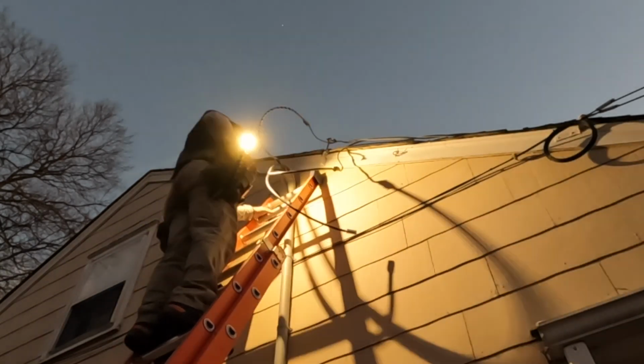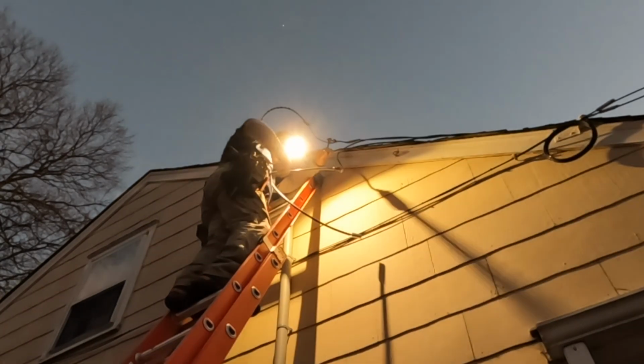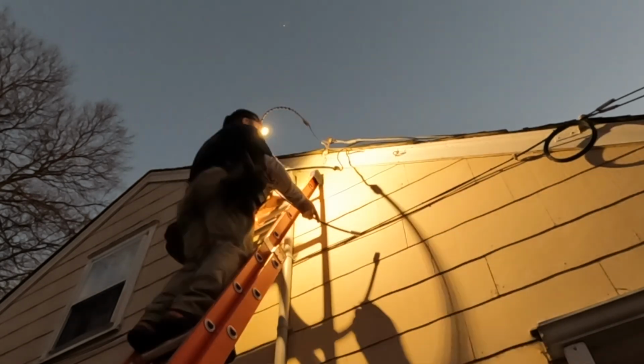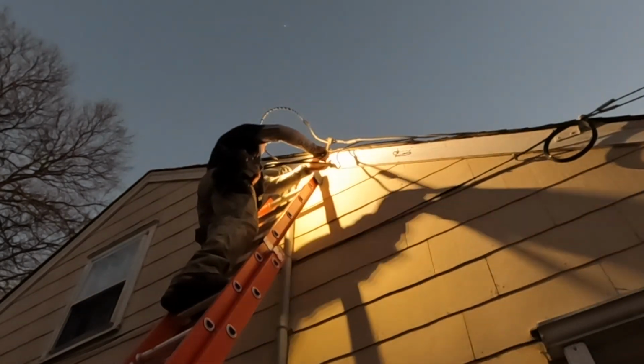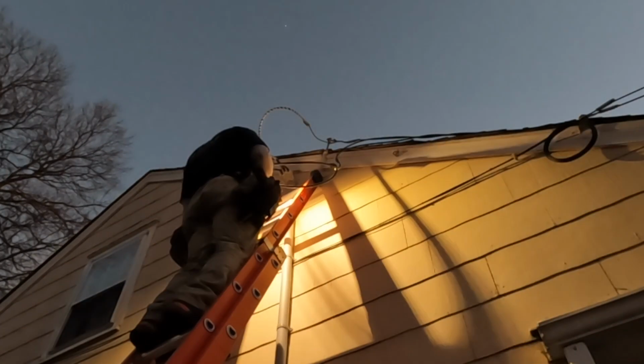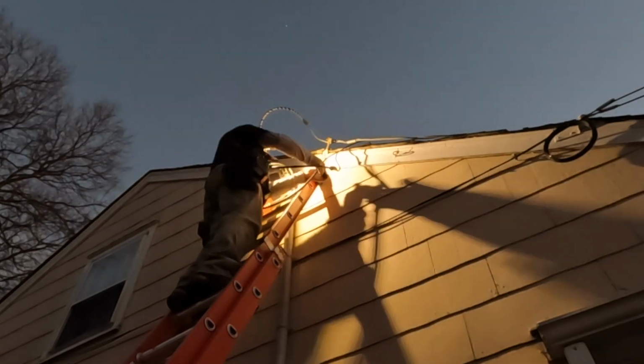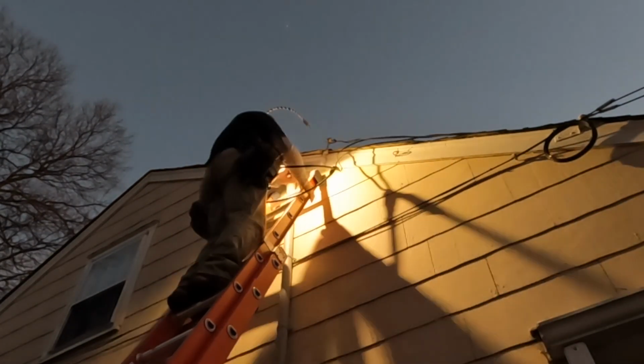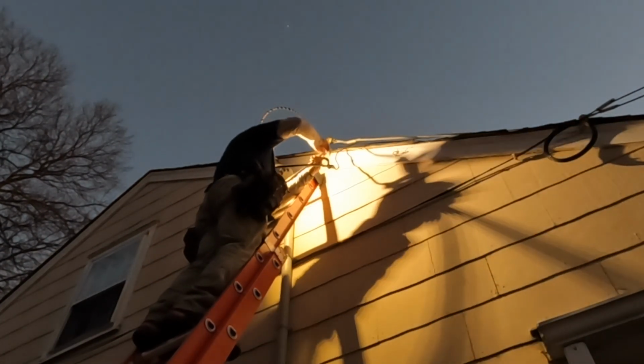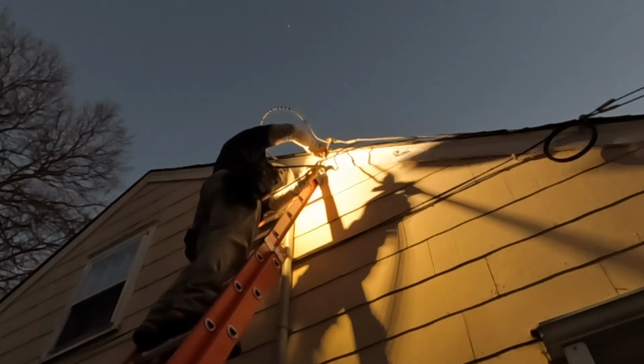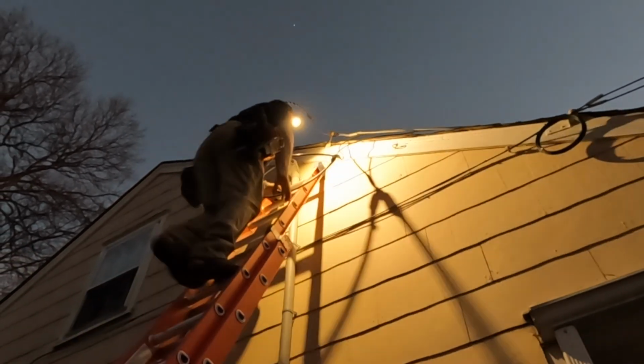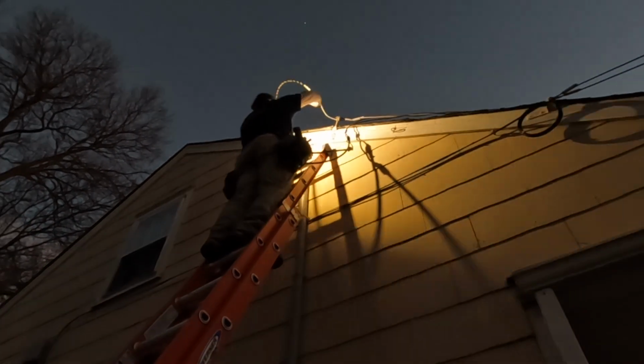And what I do is I usually connect the grounded leg first, and then both of the hots. And what I do is we tighten them down with the set screw, and then I go over them with rubber tape twice, and then come back with vinyl tape. It's really up to PSE&G if they want to come back here and resplice my connection. That's totally up to them.